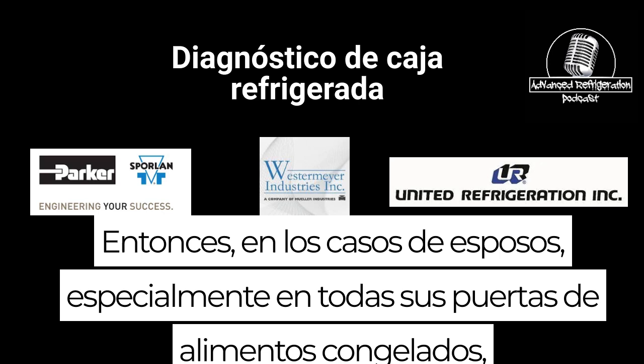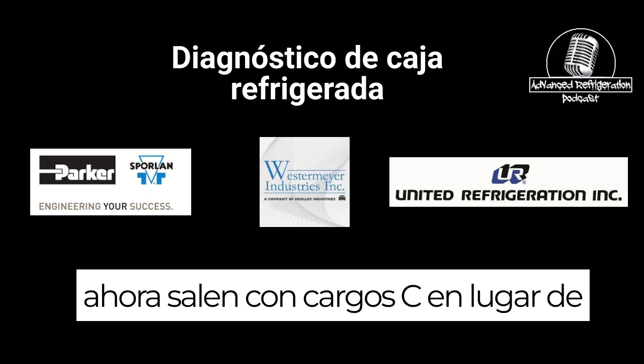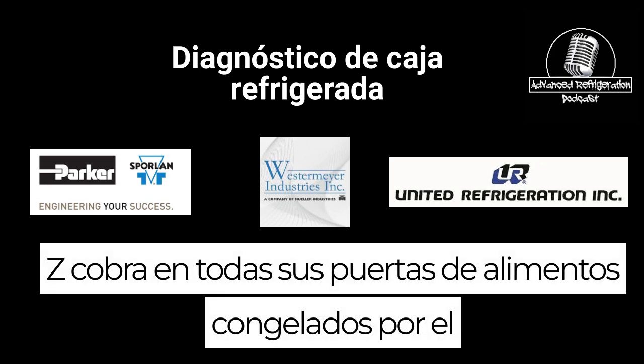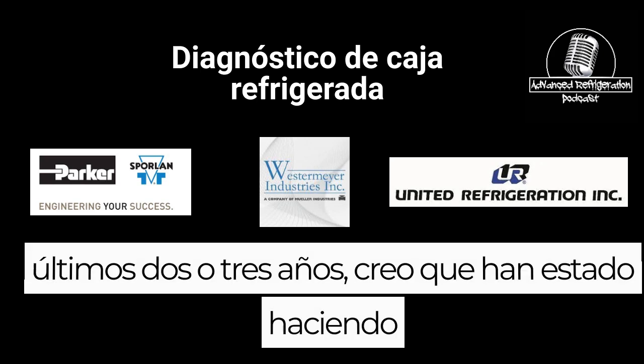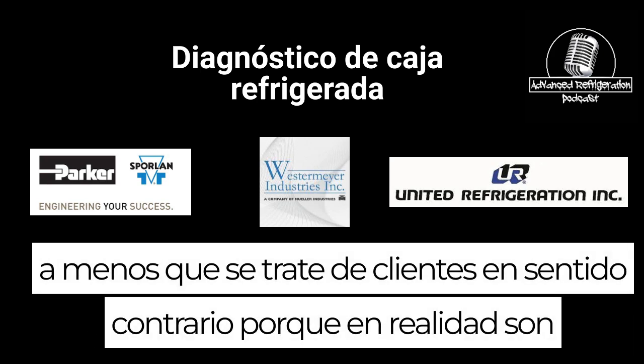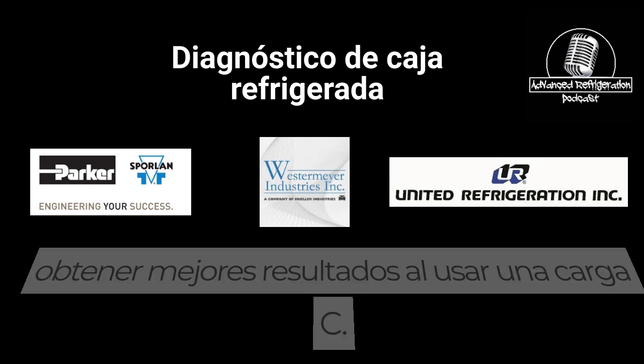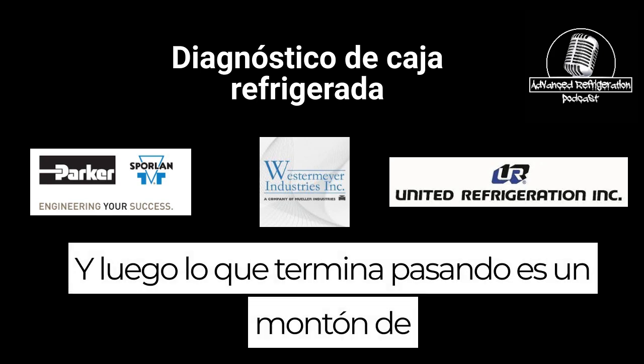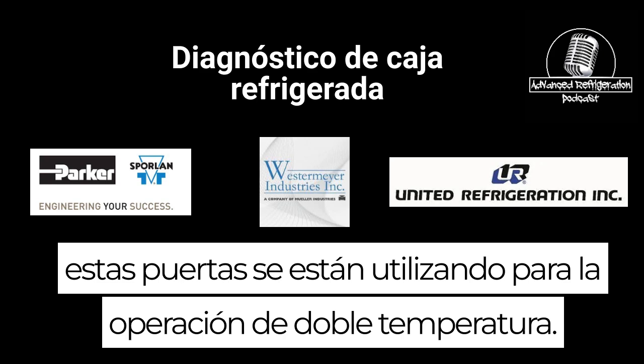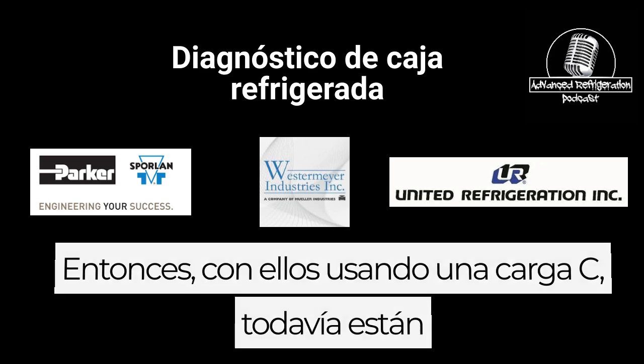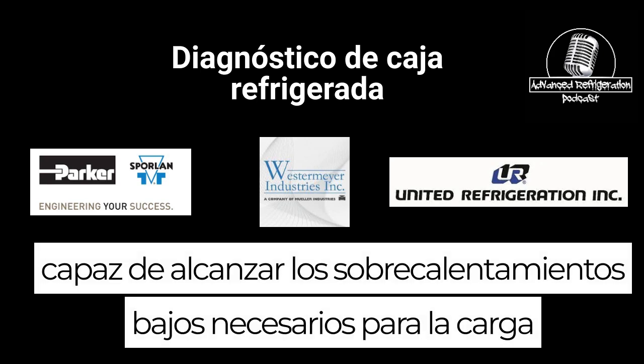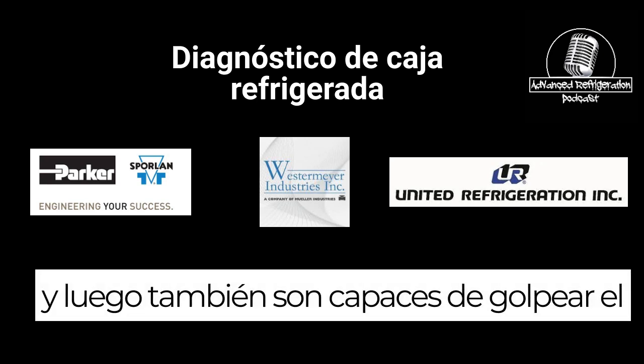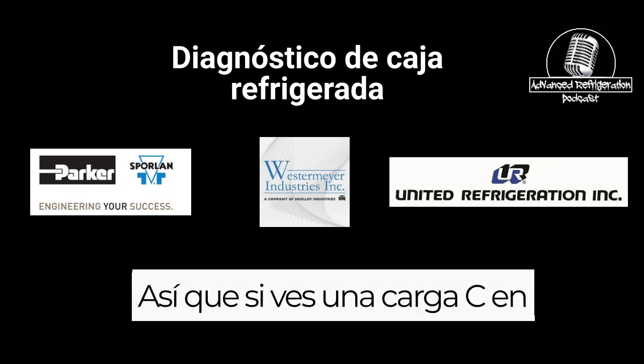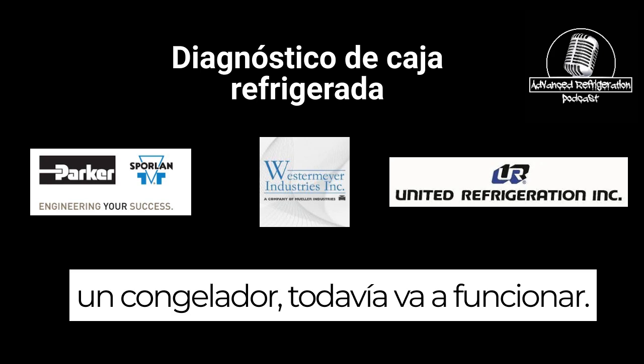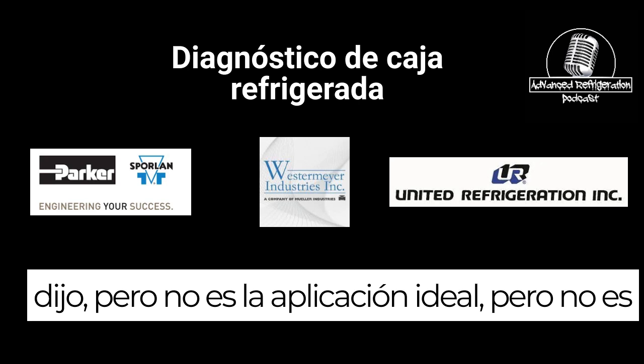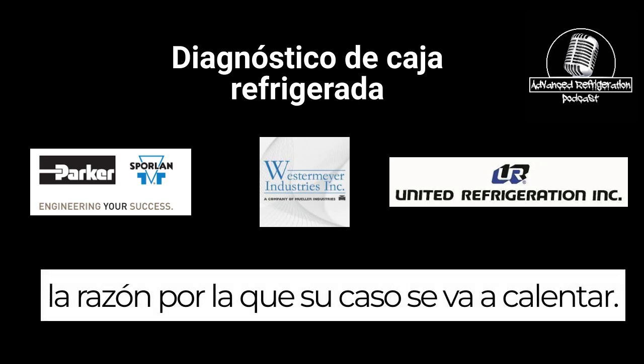On reach-in cases, especially all their frozen food doors now, they are coming out with C charges instead of Z charges, for like the last two or three years. I think they've been doing it because they're actually getting better results out of using a C charge. And a lot of these doors are getting used for dual temp operation, so being used for medium temp also. With a C charge, they're still able to hit the low superheats required for low temp, and they're also still able to hit the stable superheat for medium temp better. So if you see a C charge in a freezer, it's still going to work. It's good down to -10, like Brett said. It's not the ideal application, but it's not the reason your case is going to be running warm.